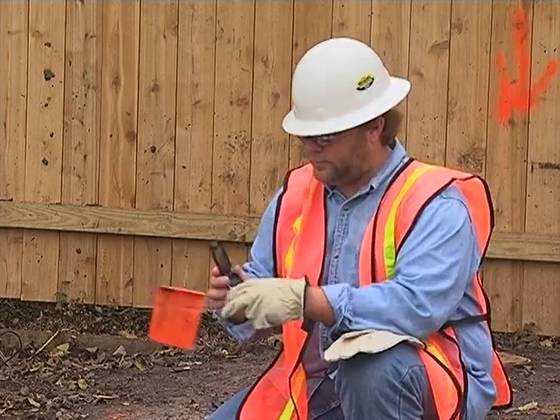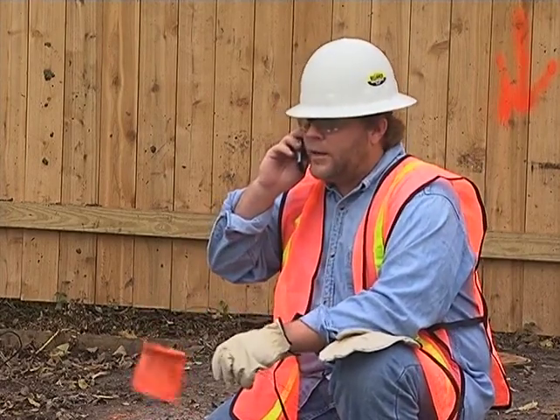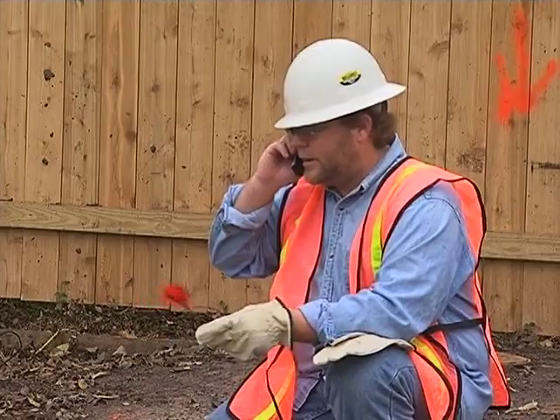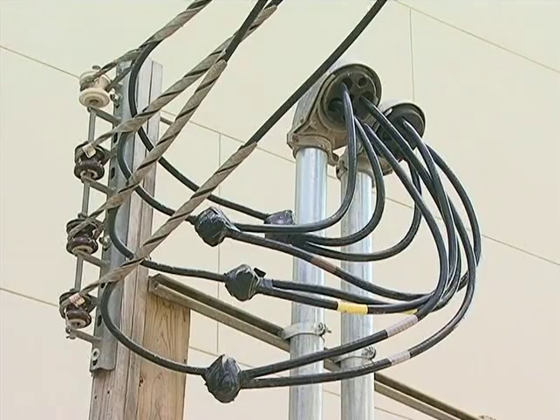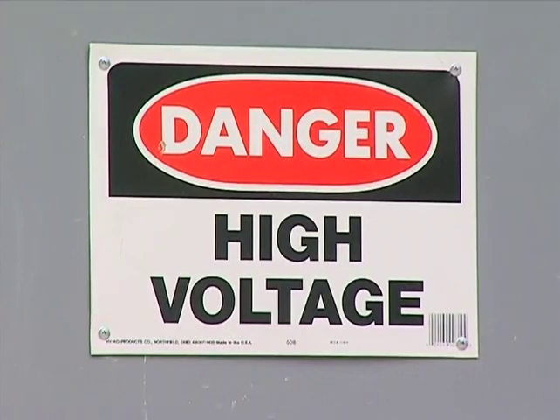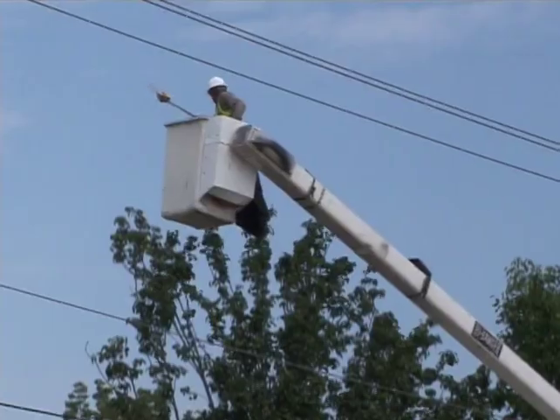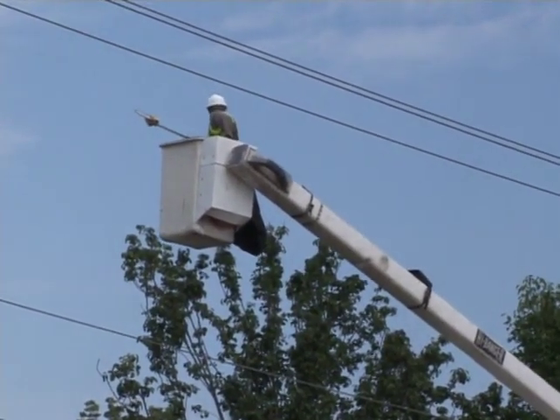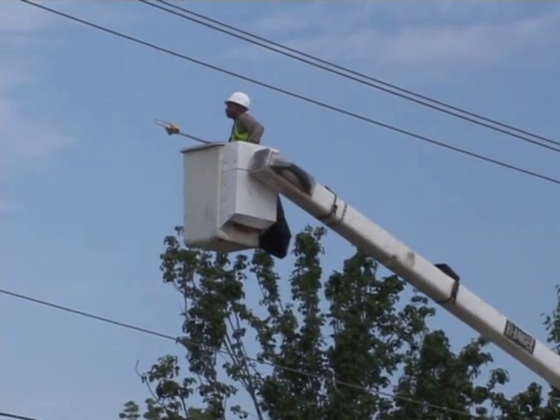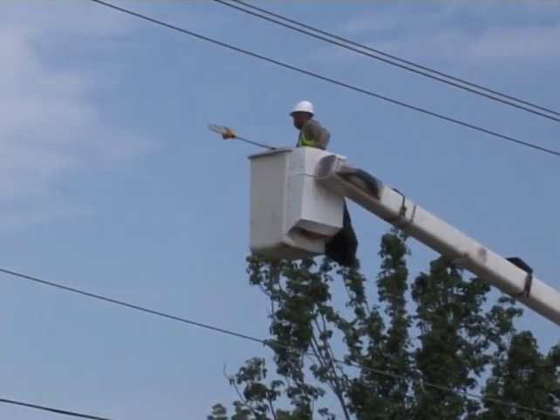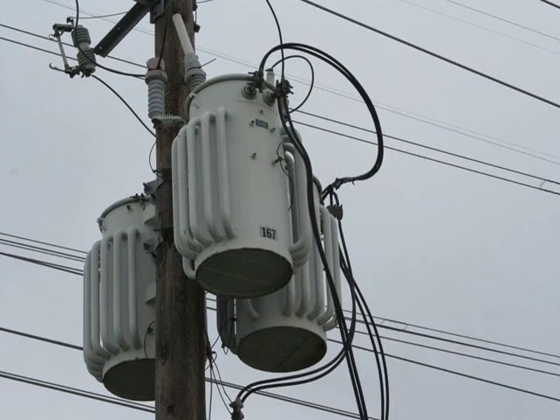Prior to working, and especially digging, contact all utilities for buried line locations. Watch for overhead lines and buried power line indicators. Observe all posted warning signs. Unqualified employees and mechanical equipment should remain at least 10 feet away from overhead lines. And always assume lines are energized.